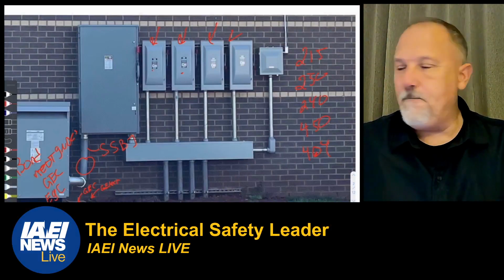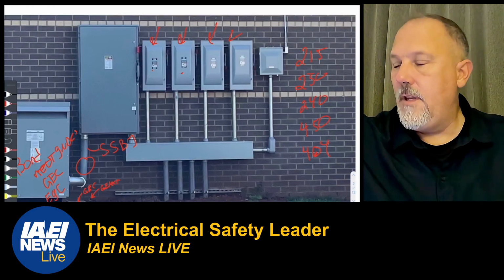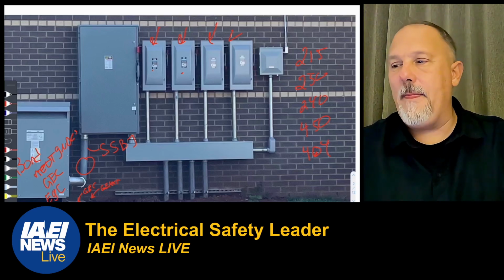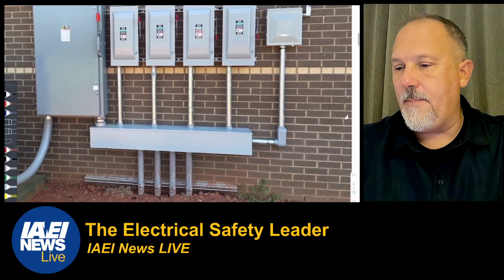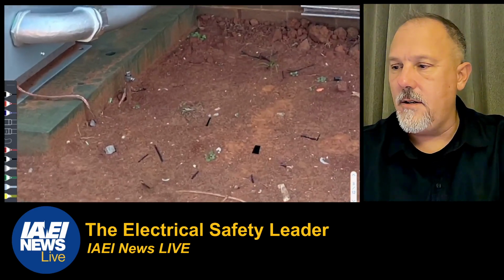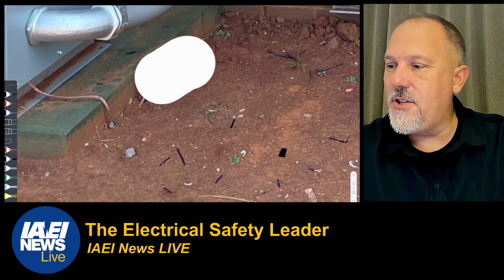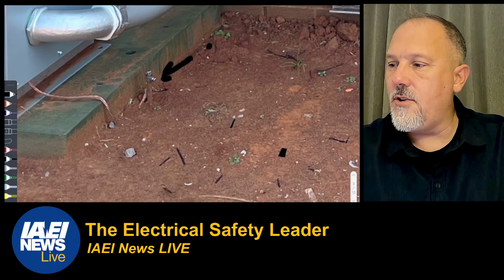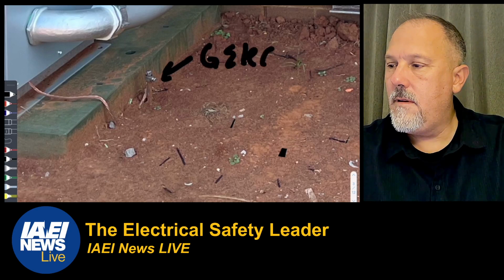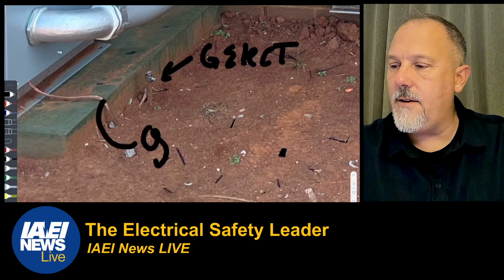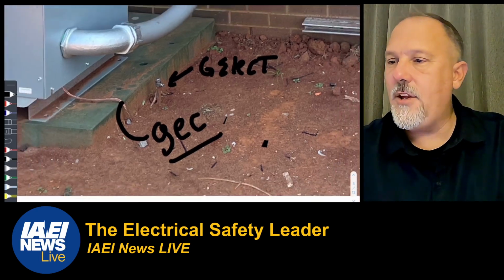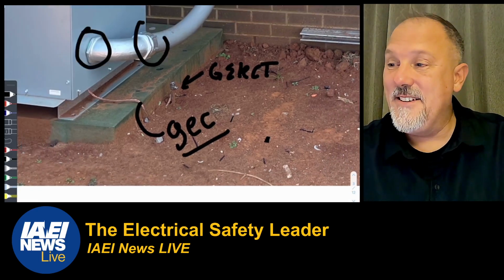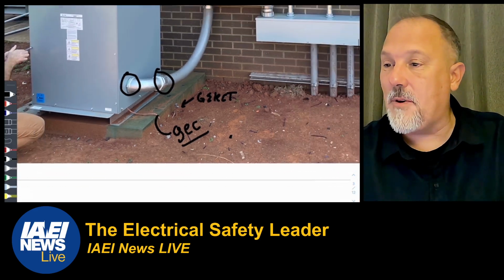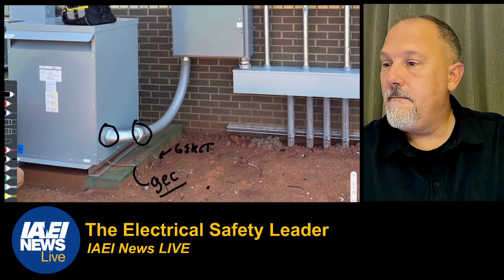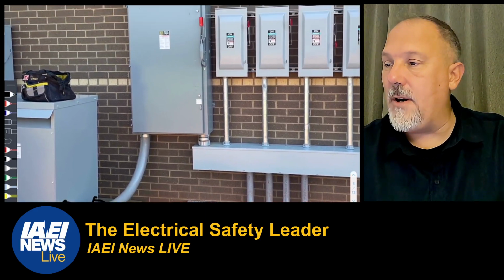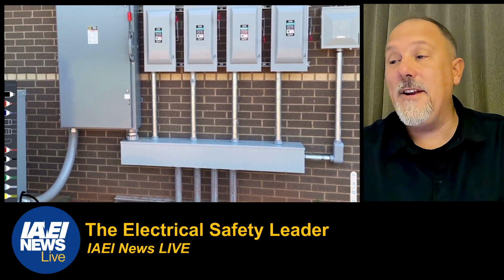All right, so okay, so pencil. All right, now here's even a better picture. There we go. Look at this picture. Look at that. Okay, so there is your grounding electrode. This is your grounding electrode conductor, right? You got a nice shot of your fittings, making sure that all of the right fittings are in place per the listing, and all of your bonding is done correctly.